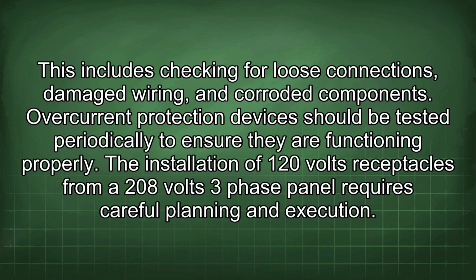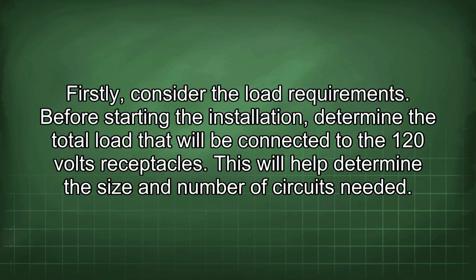The installation of 120 volt receptacles from a 208 volts three-phase panel requires careful planning and execution. Firstly, consider the load requirements. Before starting the installation, determine the total load that will be connected to the 120 volt receptacles. This will help determine the size and number of circuits needed.